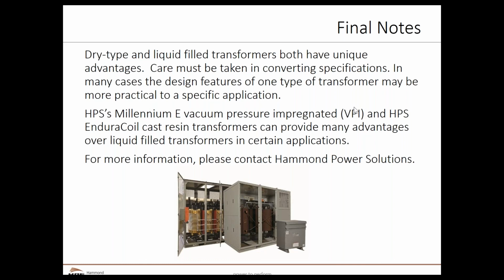Our biggest thing here is that if you do want to consider a dry type transformer for what we would normally, maybe in the past, have specified a liquid filled for, there's a lot of different design considerations you have to make to get the true advantage. In a lot of cases, there are some great advantages to liquid filled, and there are some applications that have great advantages for dry type.